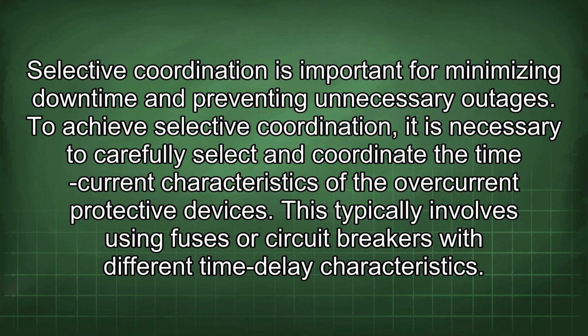To achieve selective coordination, it is necessary to carefully select and coordinate the time current characteristics of the overcurrent protective devices. This typically involves using fuses or circuit breakers with different time delay characteristics.